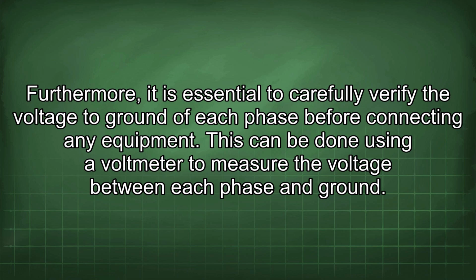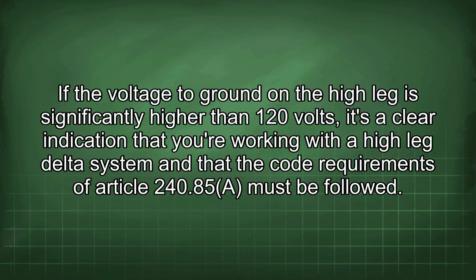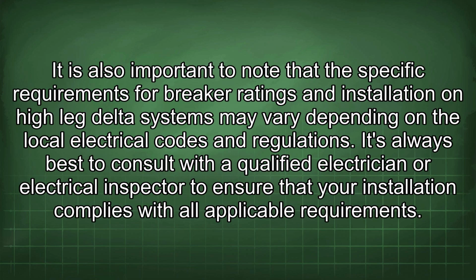Furthermore, it is essential to carefully verify the voltage to ground of each phase before connecting any equipment. This can be done using a voltmeter to measure the voltage between each phase and ground. If the voltage to ground in the high leg is significantly higher than 120 volts, it's a clear indication that you're working with a high-leg delta system and that the code requirements of Article 240.85 must be followed. It is also important to note that the specific requirements for breaker ratings and installation on high-leg delta systems may vary depending on the local electrical codes and regulations. It's always best to consult with a qualified electrician or electrical inspector to ensure that your installation complies with all applicable requirements.